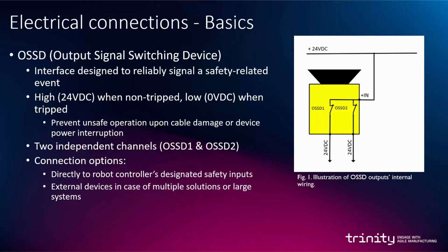The OSSD is doubled on two independent channels, which are usually labeled OSSD1 and OSSD2. This is to ensure the reliability of the safety device in a scenario where the safety violation has occurred. The OSSD may be connected directly to the robot controller's designated safety inputs, or external devices may be used in case of having multiple different safety solutions or using them in a very large robotic system.